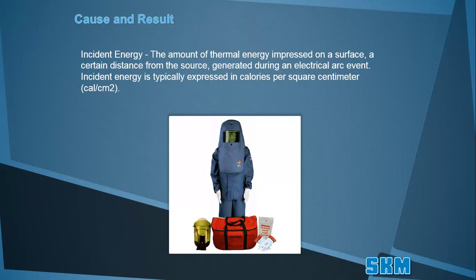To dive deeper into arc flash, we must first understand some basic terminologies. The determination of the incident energy at each equipment will provide guidance on the selection of personal protective equipment, commonly referred to as PPE. Incident energy is the amount of thermal energy impressed on a surface, a certain distance from the source, generated during an electrical arc event. Incident energy is typically expressed in calories per centimeter squared.